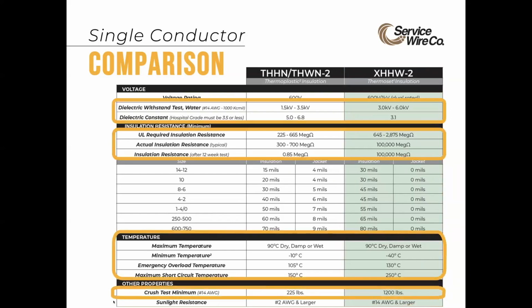In this comparison chart, you can see that Service Wire's thermoset XHHW-2 has a dielectric constant of less than 3.5, meaning the cable's insulation has a greater ability to resist leakage current. And the cable insulation resistance is substantially higher than PVC. This means the cable can handle more spikes and inrushes over longer periods of time while protecting critical circuits at risk of electrical interference from high leakage current. XHHW-2 also has a higher maximum and lower minimum temperature rating, protecting the cable in open air installations. And the thermoset XLPE compound has almost 5 times the crush resistance, proving to be a more durable cable.